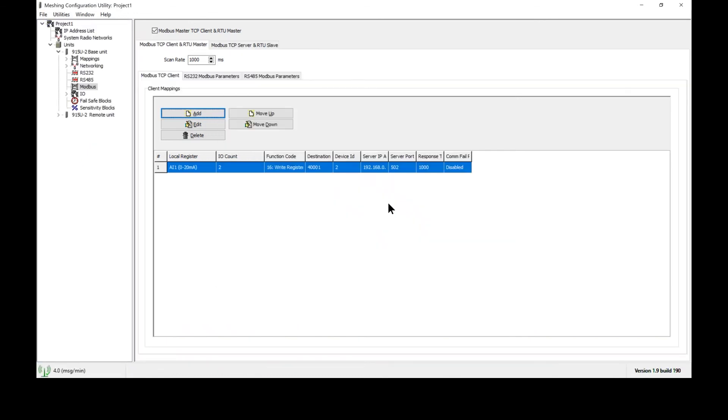Next we will change the IP address. In this case I'm going to set the IP address to 192.168.0.5. Now it's important that the IP address of the PLC match the IP address that is entered right here. It is also important that the IP addresses of the radio and the PLC be different from one another; they cannot be the same. Lastly Modbus uses port 502 so make sure port 502 is enabled on both the radio here and on the PLC.